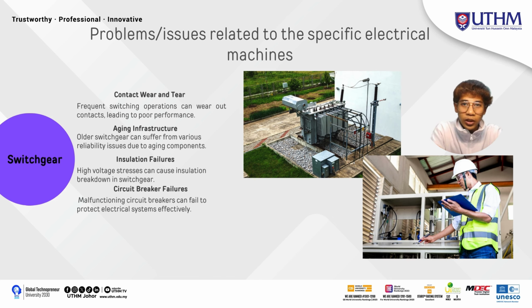So for the switchgear, we can see contact wear and tear. Frequent switching operations can wear out contacts, leading to poor performance. Then aging infrastructure. Older switchgear can suffer from various reliability issues due to aging components. Then insulation failures. High voltage stress can cause insulation breakdown in switchgear. For the last is circuit breaker failures. Malfunctioning circuit breakers can fail to protect the electrical system effectively.